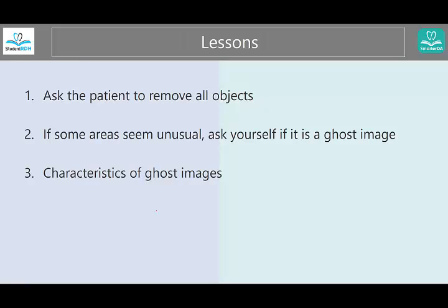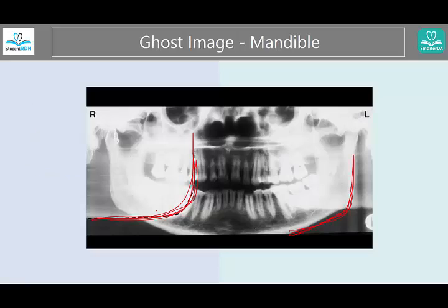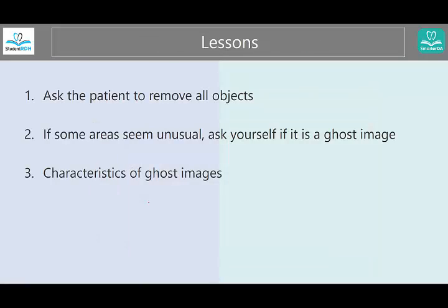The lesson here is first to ask the patient to remove any object that is in the way. If you see some unusual areas that are too white or too dark, ask yourself: is this a ghost image, rather than alerting the patient or dentist that something is wrong. To review, the three characteristics of ghost images are: number one, blurry; number two, higher up; and number three, on the opposite side.